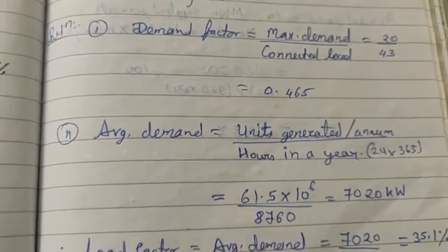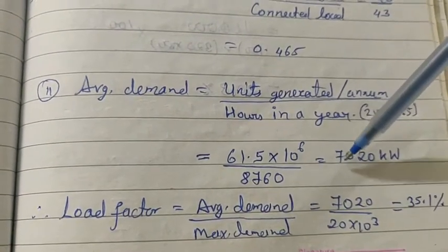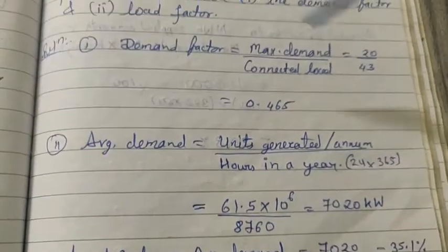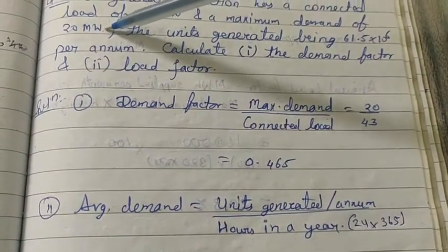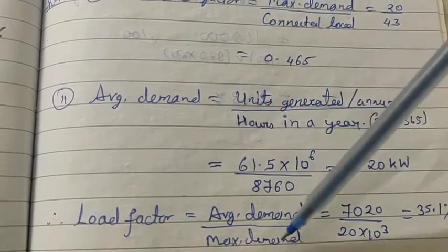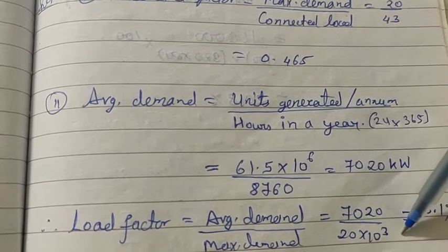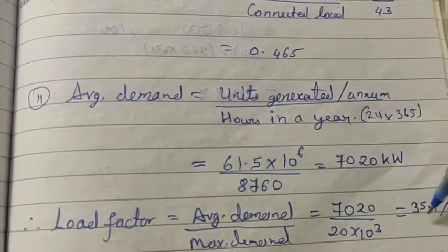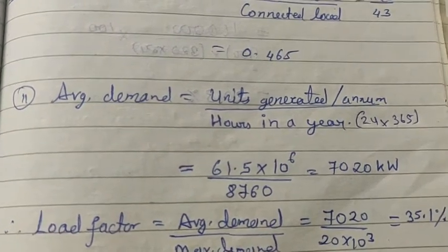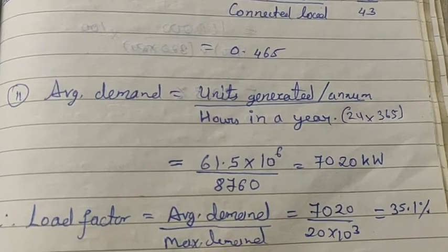Load factor equals average demand divided by maximum demand. Average demand is 7020 kilowatt, and maximum demand is 20 megawatt, which we convert to kilowatt as 20 × 10³ kilowatt. Both units cancel out, and the load factor comes out to be 35.1%. Thank you.